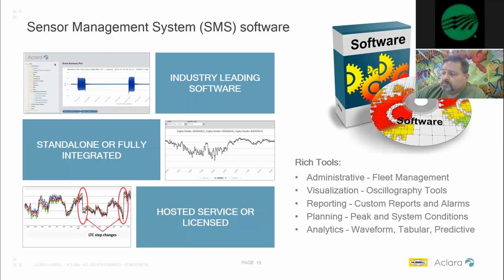The SMS also provides custom reports available for all the types of events captured and reported by those sensors. These reports, as Gary mentioned earlier, include power off type events, momentaries, faults, line and power disturbances, as well as high current alarms, and these all come back in real time. Whenever these events are triggered by the sensor itself, they're collected and sent back into the SMS interface, where we manipulate them through our algorithms to give the user an answer they can use to understand what's happening on that particular feeder.